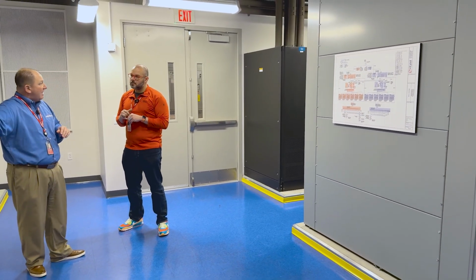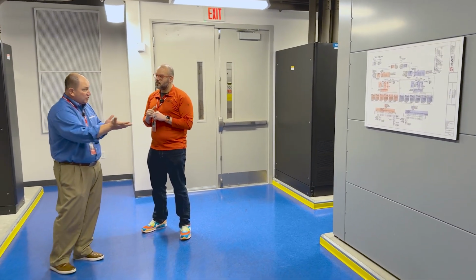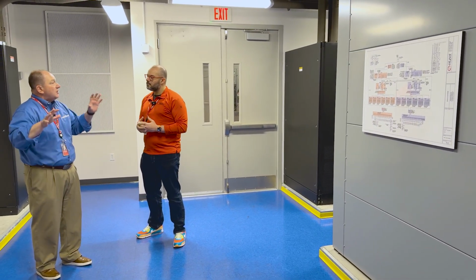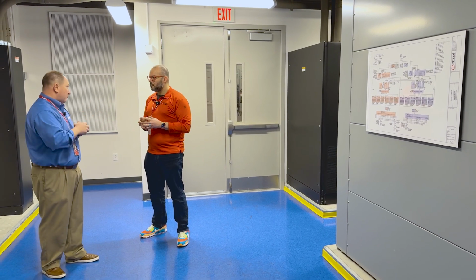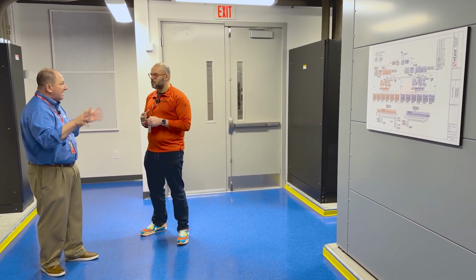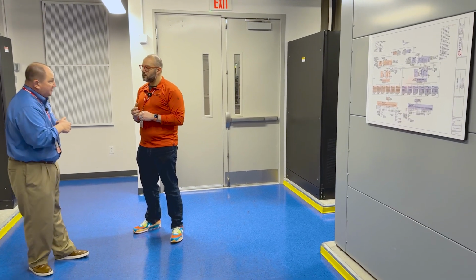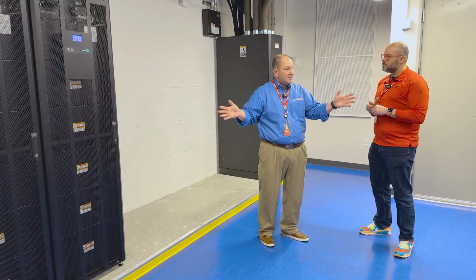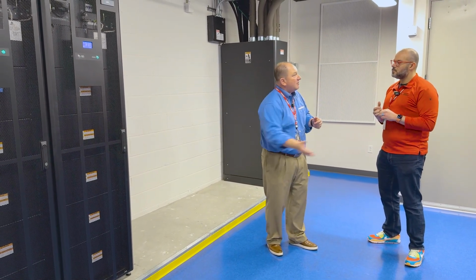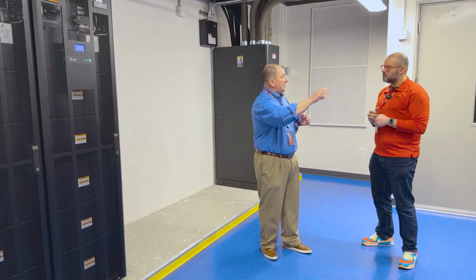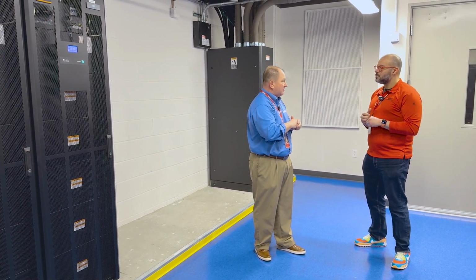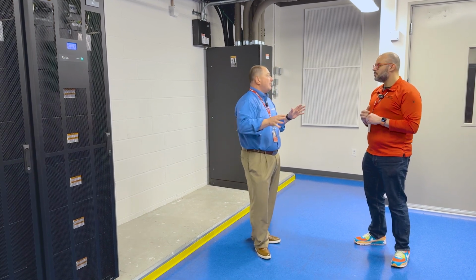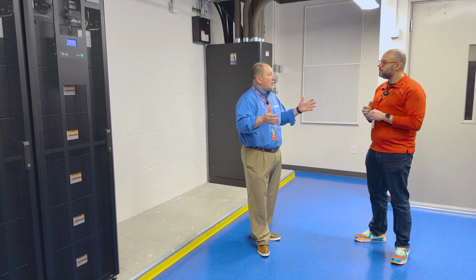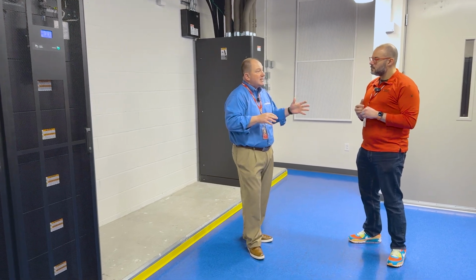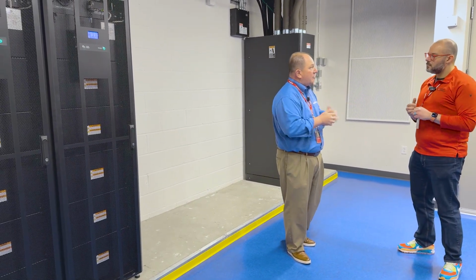So the battery plant we have here - we talked about the transfer switches and the transfer between commercial and generator power. The UPS makes that happen without any interruption to the raised floors, so clients never see any of that. Upon a power interruption, the transfer switch senses that commercial power has gone away, but the UPS is connected and the batteries discharge, providing power to the UPS, which in turn provides power to the raised floor until the generator comes back on. Our battery plant today is capable of carrying the load for 15 minutes without commercial power coming back, and we're basically up on the generator within a minute - that's our time sequence here at Expedient.